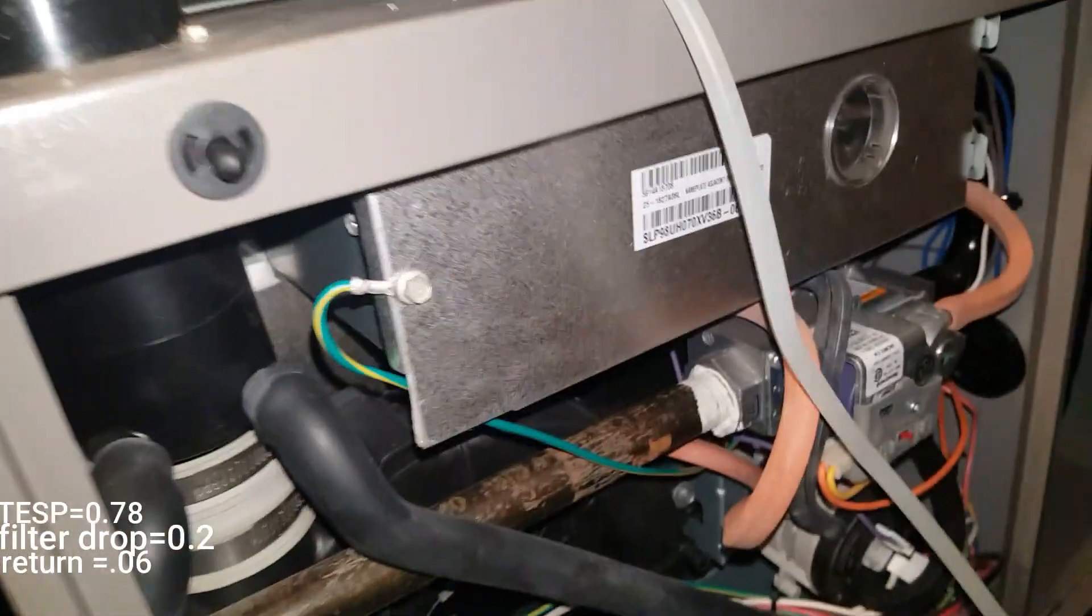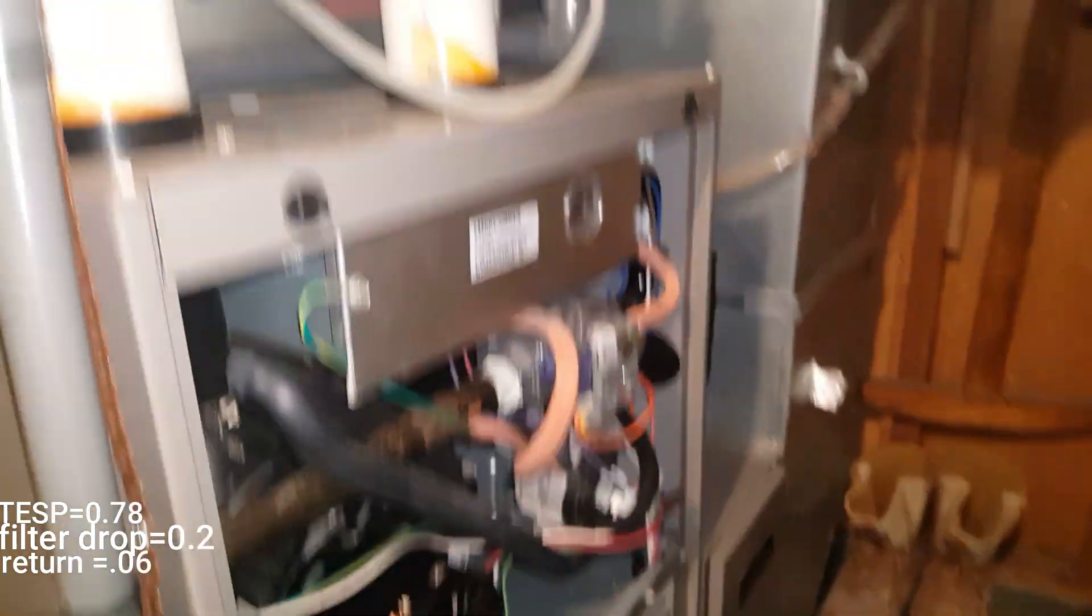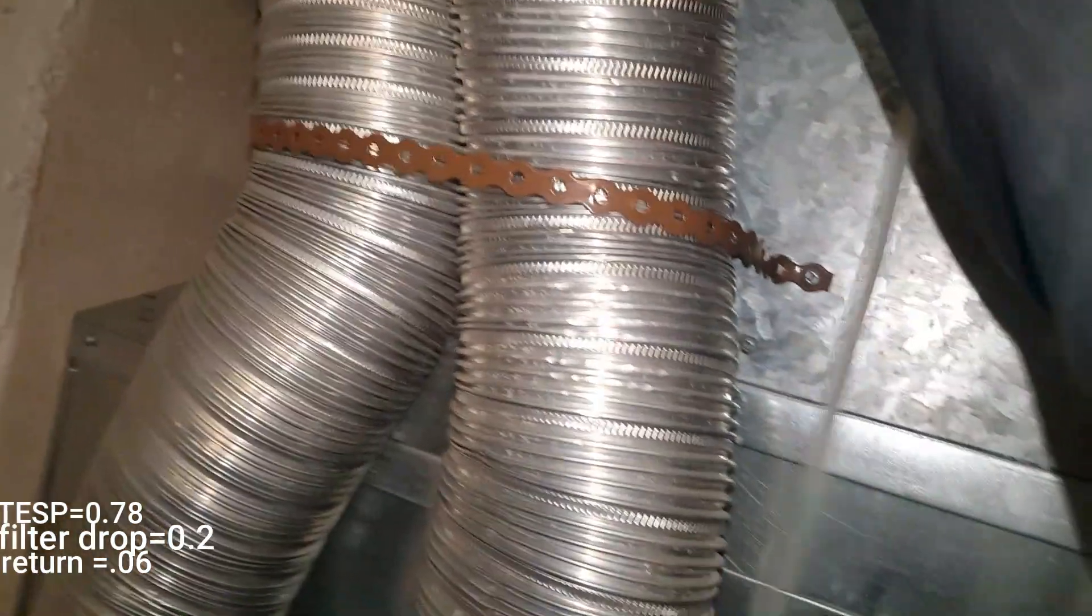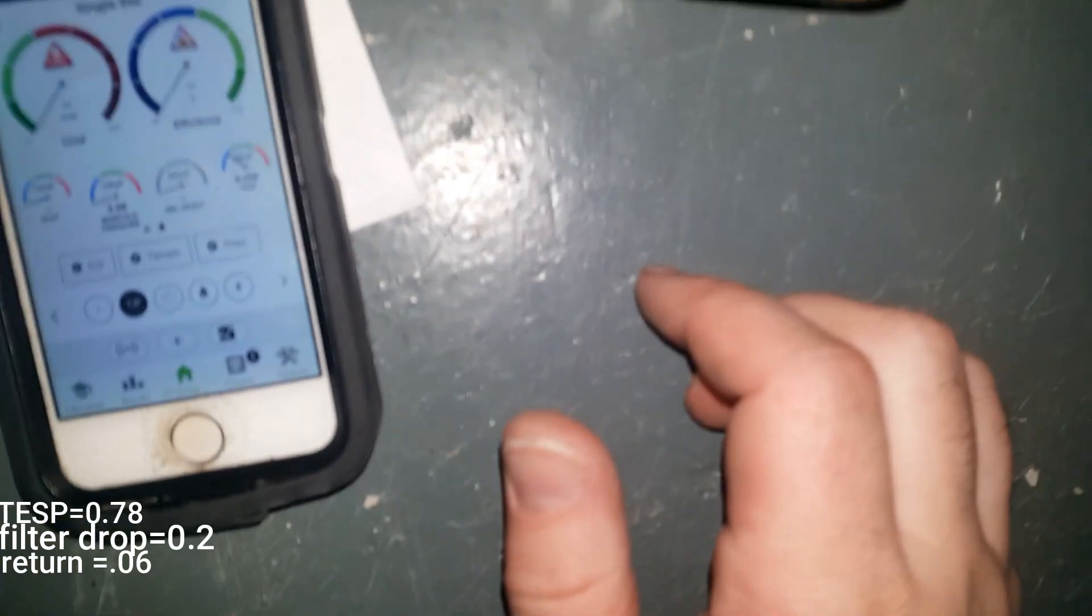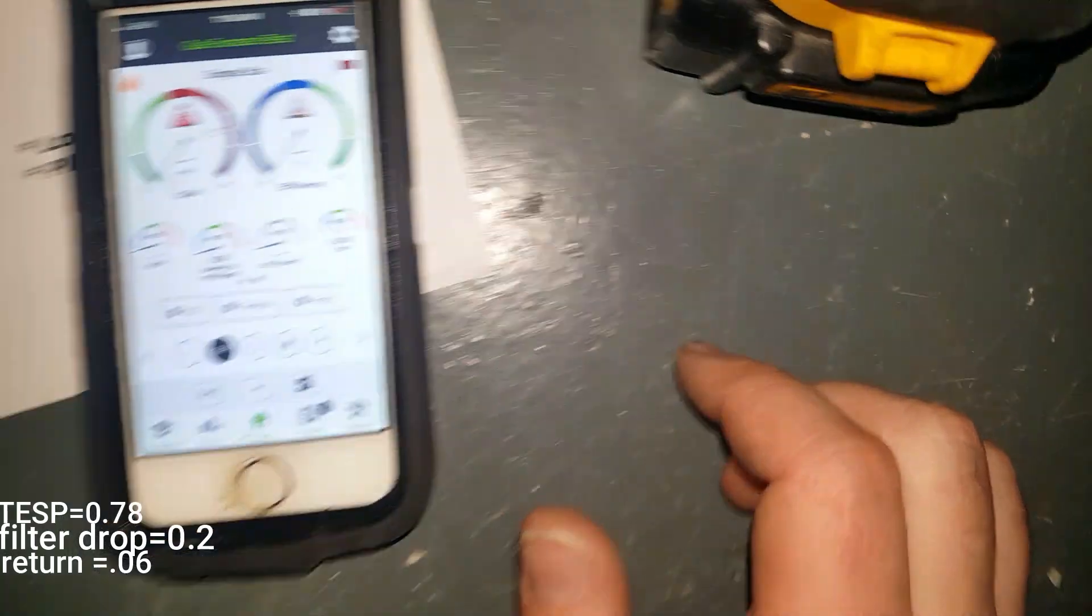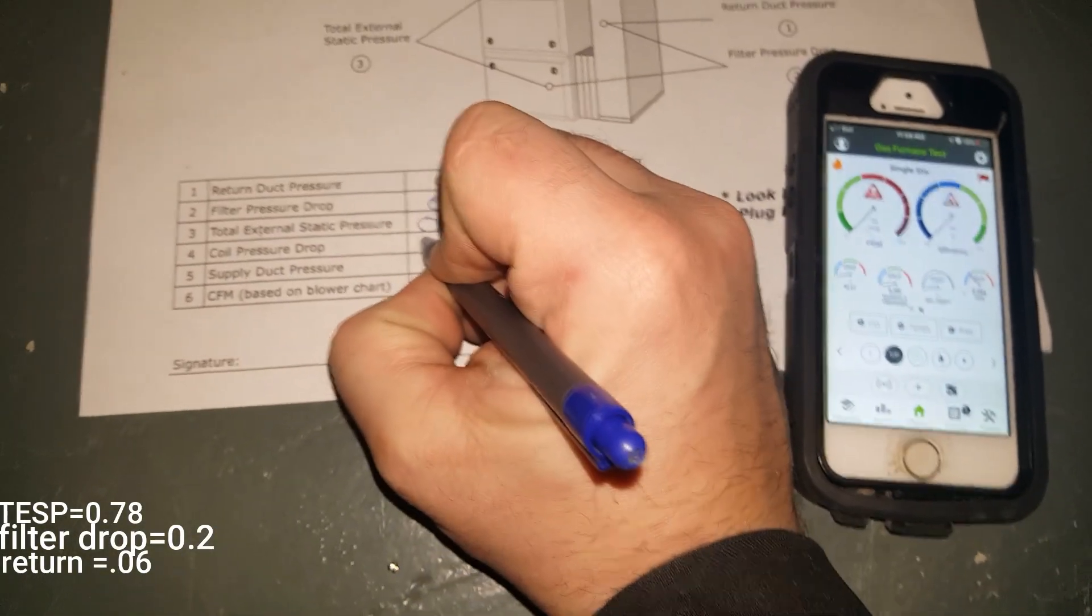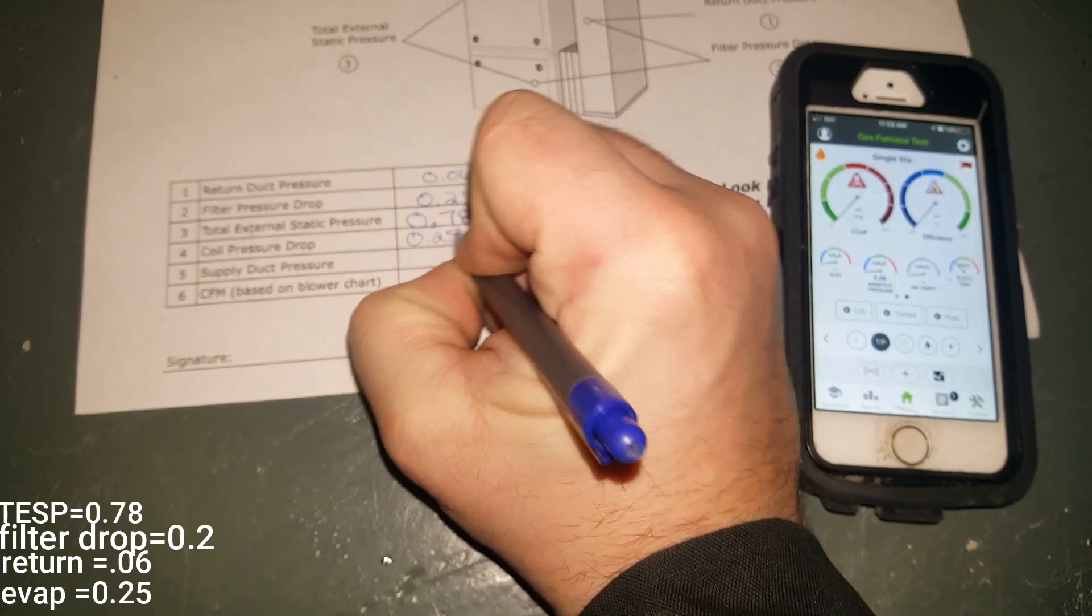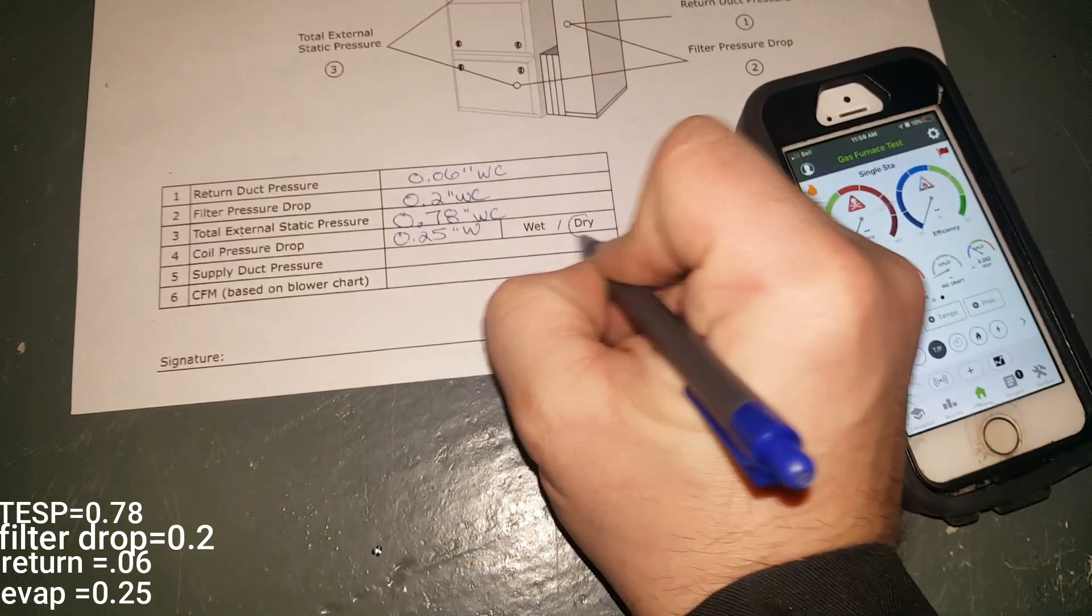Next thing I'm going to do is my evaporator pressure drop. Just like that. And my pressure is 0.25 on a dry coil.